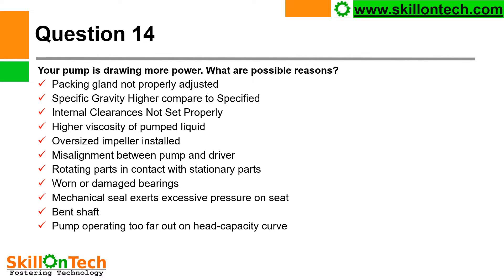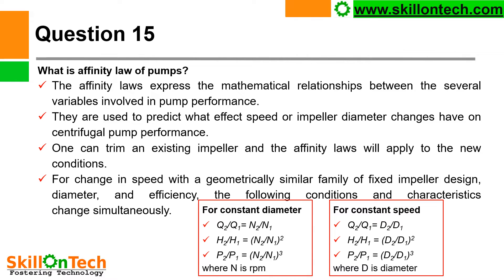Pump operating too far out on the head-capacity curve: if your pump is not operating at the best efficiency point, it will also draw more power. These are some important reasons for a pump drawing more power from its prime mover.